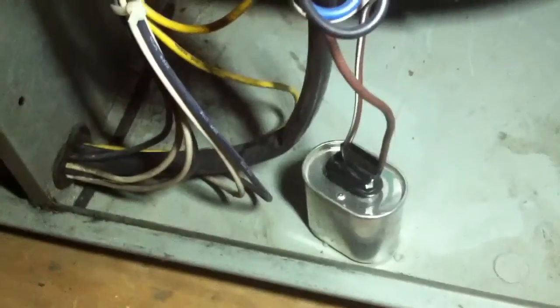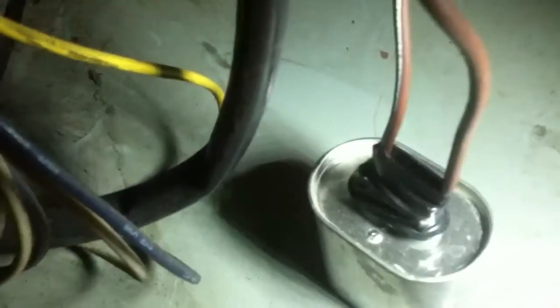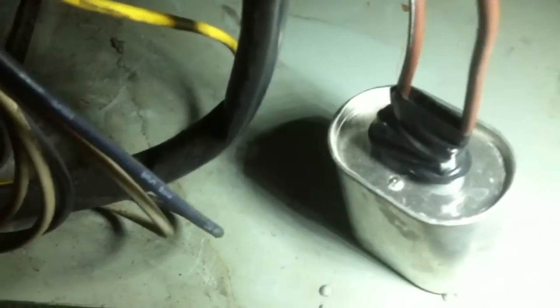I'm going to have to strap back the capacitor. It looks like the run cap bandit hit this place — they just have this thing hanging, which is nice. And of course they decided to go ahead and put some tape all around the terminal, so that'll make it nice and safe. I'm going to go ahead and strap it to the blower housing, get that mounted up nice and properly.